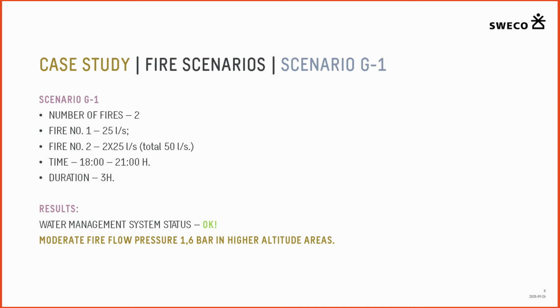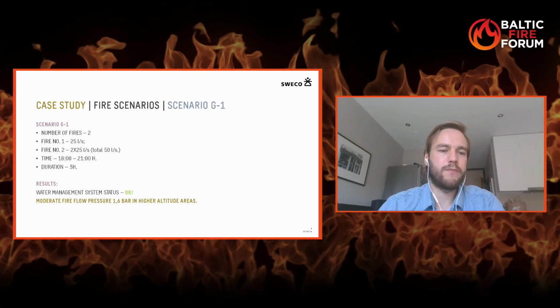And it's very important to say that we test the fire during the time from 6 to 9 p.m., when the water demand from the whole city is higher. So the total fire duration is 3 hours.